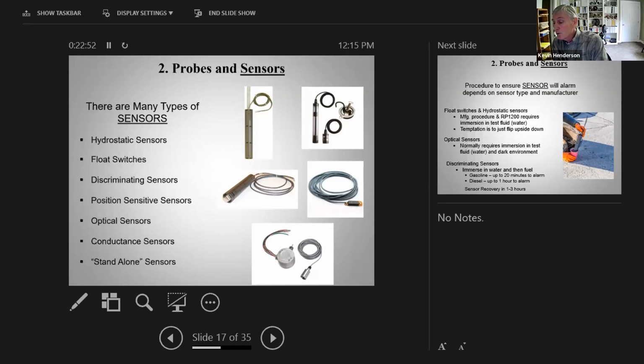All they are is a little float switch. They do not discriminate. All they can do is tell you there's liquid in the sump or in the tank. Interstitial, they're just float switches. That's all they are. We do have some hydrostatic monitors. Of course, that's the top right picture. Don't see any standalone sensors. That's the bottom picture. The middle right picture, that's a tank interstitial sensor. And boy, that one is trouble. That's a lot of fun to deal with there. But almost all of them are just non-discriminating float type sensors.